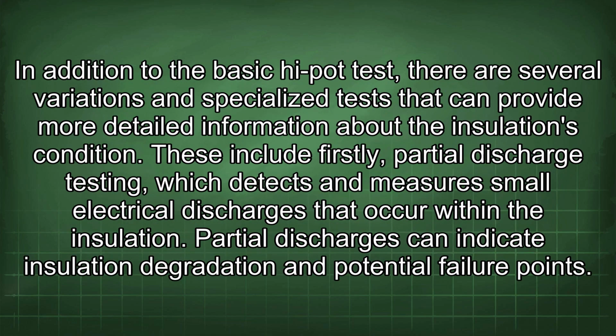In addition to the basic hi-pot test, there are several variations and specialized tests that can provide more detailed information about the insulation's condition. These include, firstly, partial discharge testing, which detects and measures small electrical discharges that occur within the insulation. Partial discharges can indicate insulation degradation and potential failure points.